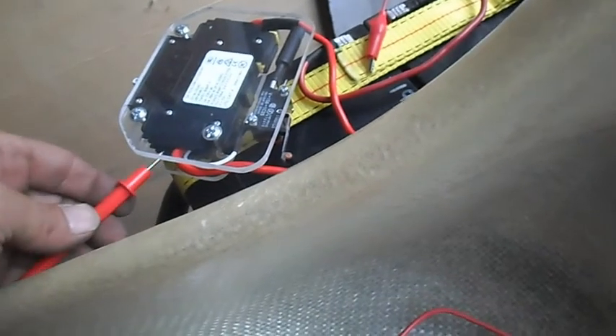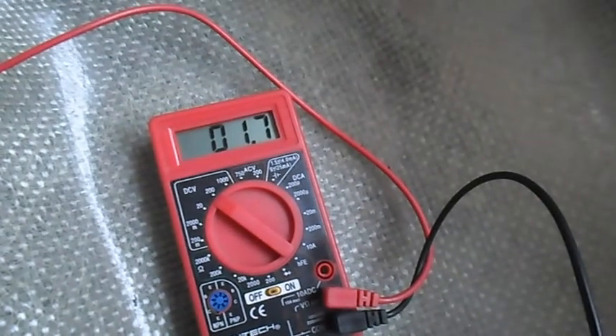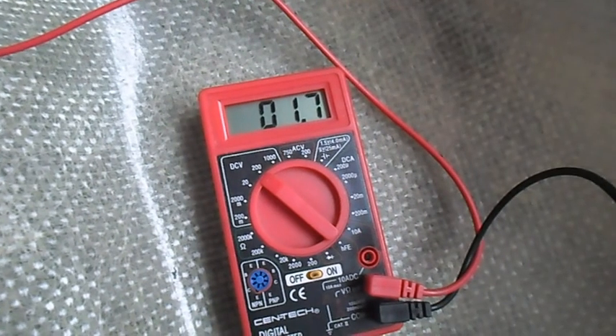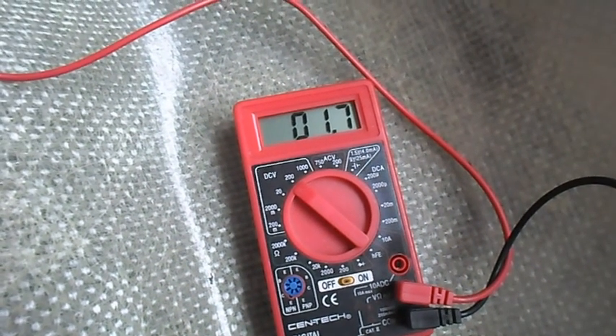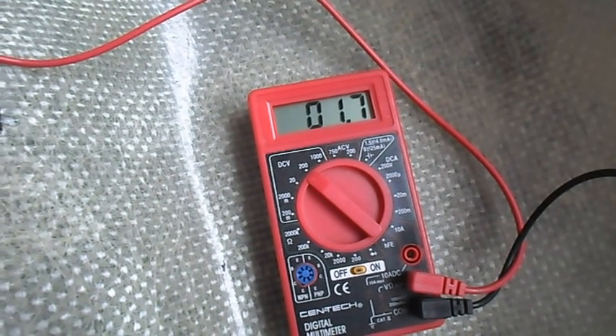Right now the contactor is off, and therefore on this side of the contactor we're showing 1.7. That must be the residual current in the capacitors in the speed controller back here.